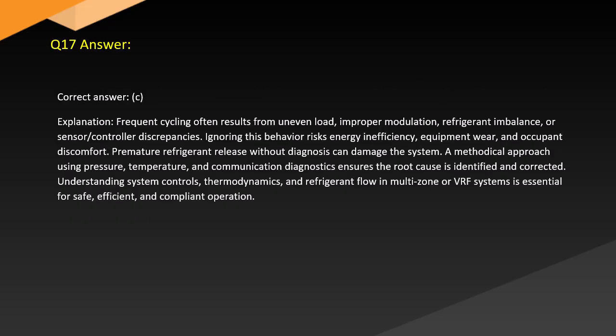Answer. Correct answer: C. Explanation. Frequent cycling often results from uneven load, improper modulation, refrigerant imbalance, or sensor and controller discrepancies. Ignoring this behavior risks energy inefficiency, equipment wear, and occupant discomfort. Premature refrigerant release without diagnosis can damage the system. A methodical approach using pressure, temperature, and communication diagnostics ensures the root cause is identified and corrected. Understanding system control, thermodynamics, and refrigerant flow in multi-zone or VRF systems is essential for safe, efficient, and compliant operation.